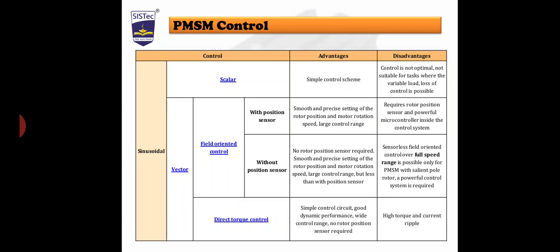The drawback of sensorless field oriented control is that operation over the full speed range is possible only for permanent magnet synchronous motors with a salient pole rotor, and a powerful control system is required, making it costly. For direct torque control, the advantages are a simple control circuit, good dynamic performance, wide control range, and no rotor position sensor is required.